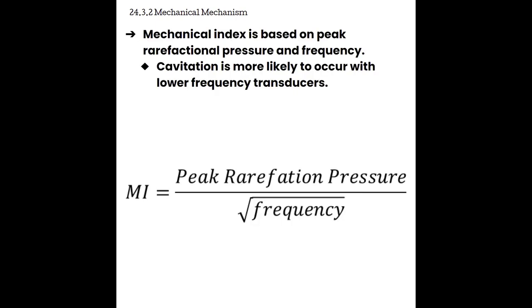Mechanical index is based on the peak rarefaction pressure and frequency. And we'll see that the likelihood of cavitation to occur is going to increase as we lower the frequency. From our formula here, the mechanical indice is equal to the peak rarefaction pressure divided by the square root of the transducer frequency. We can see that peak rarefaction pressure is directly related to the mechanical index. So if there is more pressure, it's going to cause a higher mechanical index. We also see that frequency is inversely related to the mechanical index. So if we lower our transducer frequency, we will see an increase in the mechanical index value. Lower frequencies are going to make it more likely that cavitation will occur.